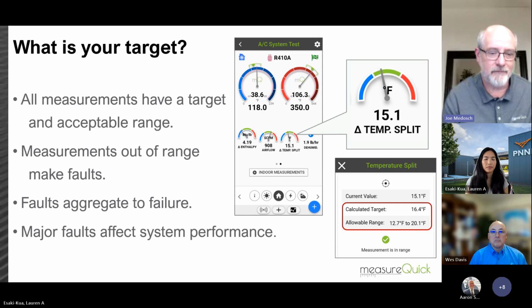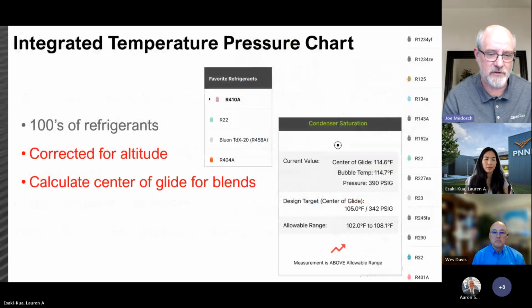Here's my split, and if I tap on that individual gauge, it pops up the screen you see on the right. The more failures you have, the more problems the system clearly has. So the more I can identify them quickly and move through them, the more I can correct them right at the install or even at the service. Not everything needs to get replaced. The goal is, can we actually do accurate measurements, determine the cause, correct it, or recommend replacement? The goal isn't to just replace anything we show up for.